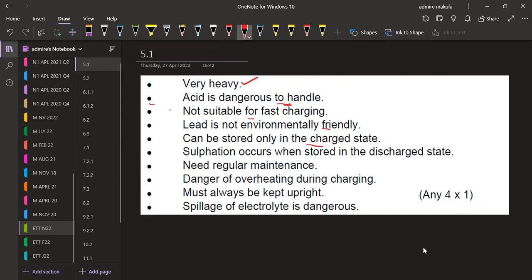Sulfation occurs when stored in the discharged state. They need regular maintenance — you are going to have regular maintenance. There is a danger of overheating during charging, and they must always be kept upright. Spillage of electrolyte is also dangerous.